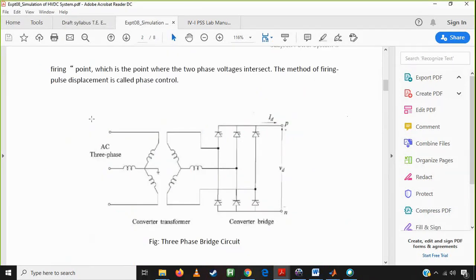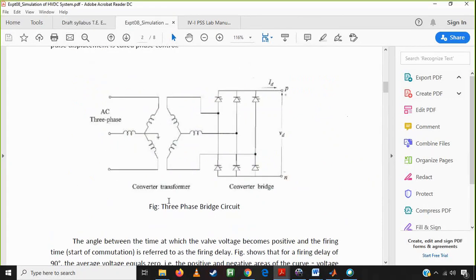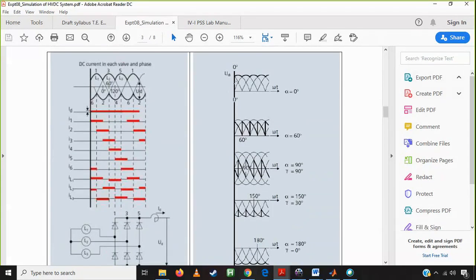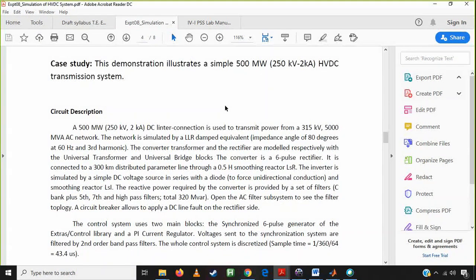Today our main focus is to transmit a bulk amount of power using the bridge converter. Here we are using the 6-pulse bridge converter. The main important components of an HVDC link are the sending end substation and the receiving end substation. The sending end substation is considered the rectifier unit, and the receiving end has the inverter unit. This is a converter system consisting of a converter transformer and a converter bridge. The main focus is the 6-pulse bridge converter, which produces 6 pulses as output.